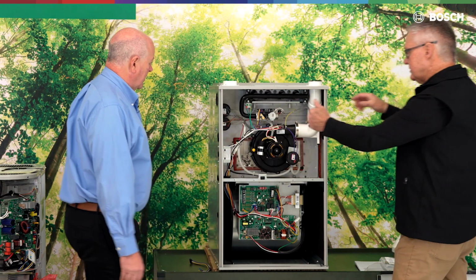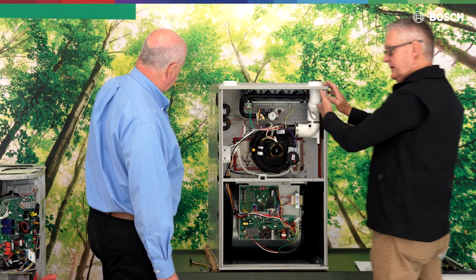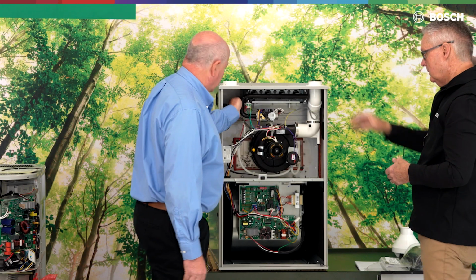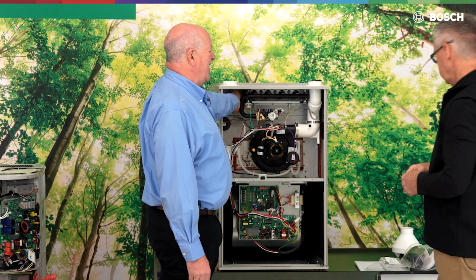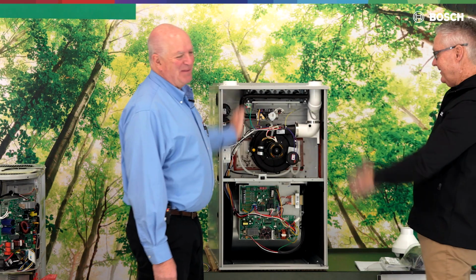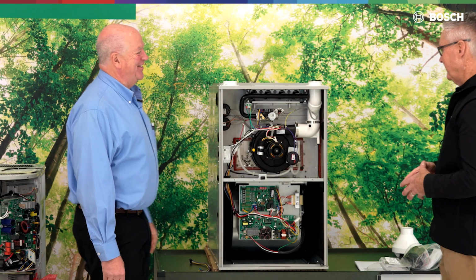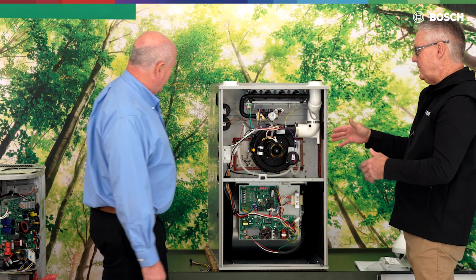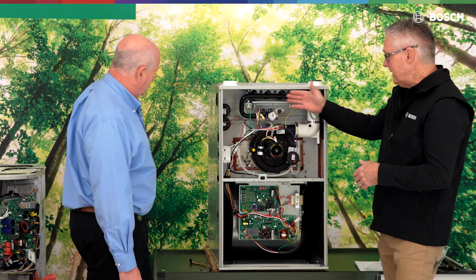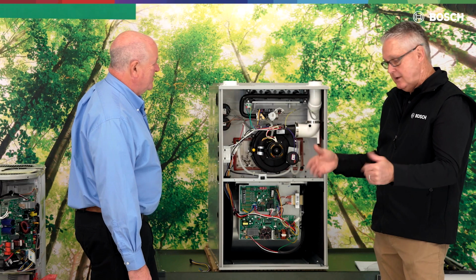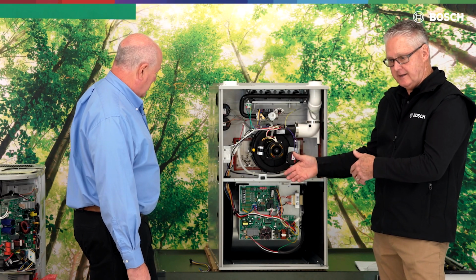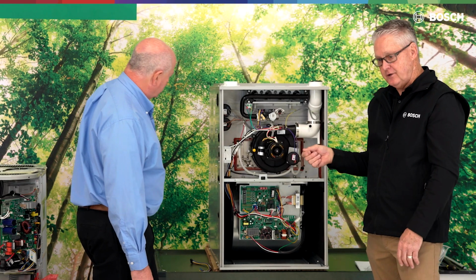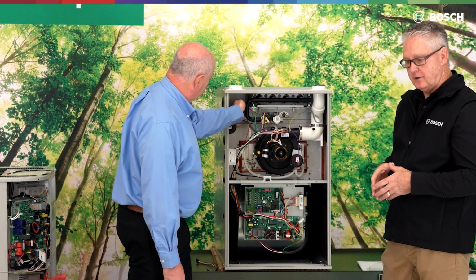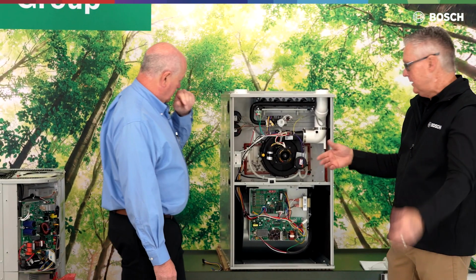Now, is the rollout sensor a manual reset? They are not. I don't think it is. I don't know if there's not. It is manual reset. Oh, it's manual reset. Okay. So when that rollout sensor is tripped, my fan is going to run all the time. I can't turn it off unless I unplug the unit. And that's when Mrs. Jones is going to call and say, listen, my fan's on, blah, blah, blah.